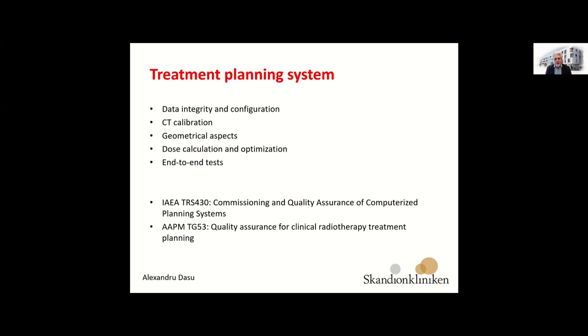We are all talking about various volumes for the target and for the organs at risk, but these come up from a succession of points delineated on an image. And depending on the manufacturer, or even for the same manufacturer, there are algorithms that define the interpolation and actually the extrapolation of the delineations in the volume. And therefore, you have to check that you have more or less the same volumes for some structures as you go on, for example, through an upgrade or after a change in the system.